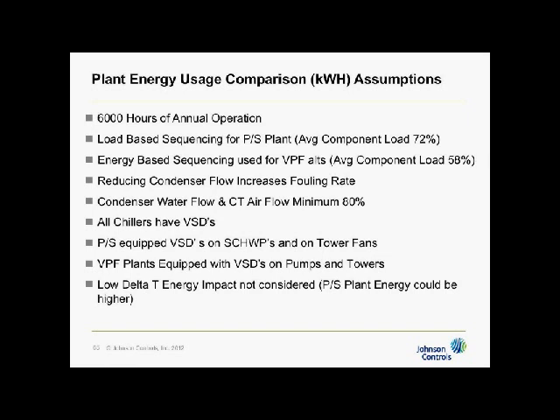We reduced our condenser water flow, but we also know that when you reduce condenser water flow, you get an increase in your fouling rate. We took that into account. Condenser water flow rate and cooling tower fan flow, we reduced to 80%. Now, we looked at several different reductions. We looked at 90%. We looked at 80%. We took it down to around 70% where we saw a crossover. There are many considerations. We'll get into that later on. But we ended up at 80% of the condenser water flow and cooling tower airflow.